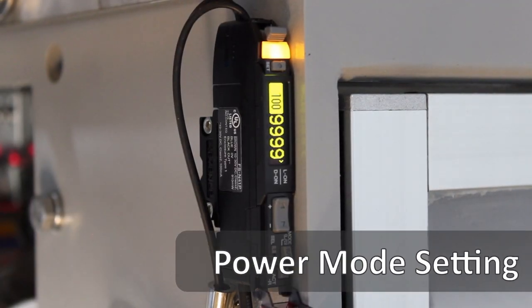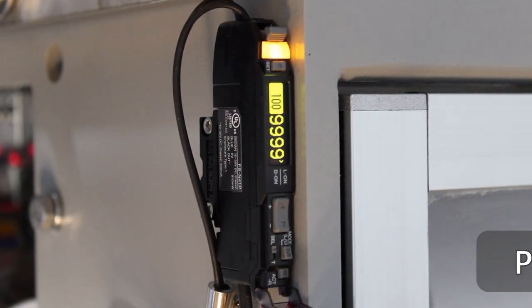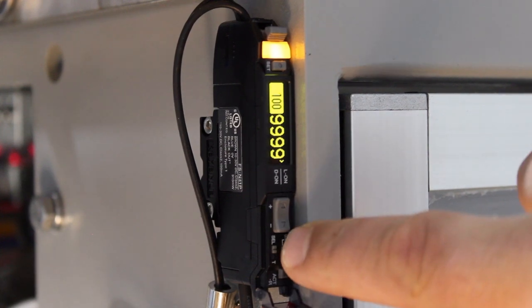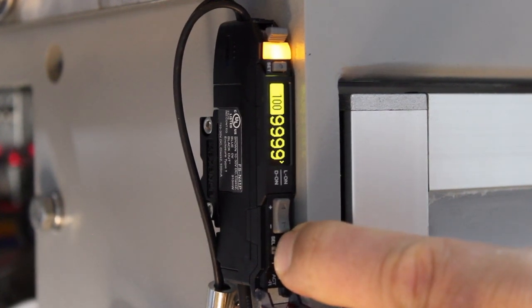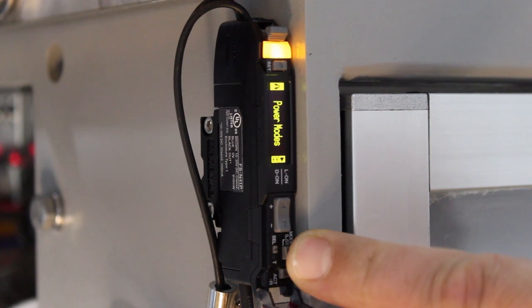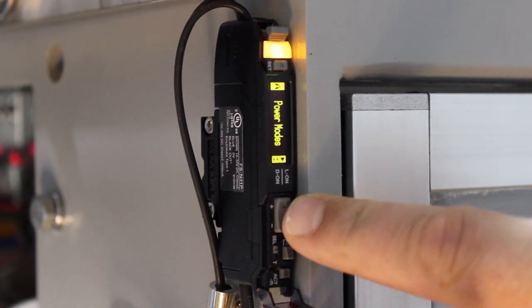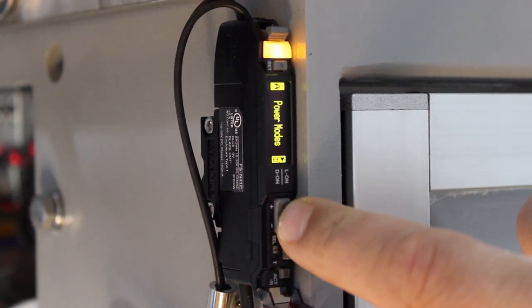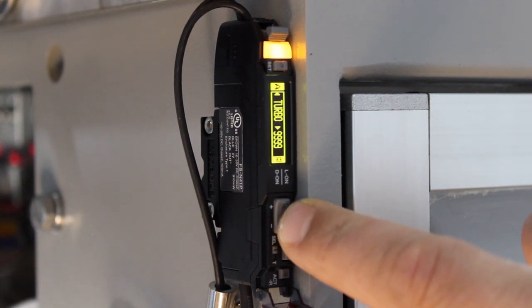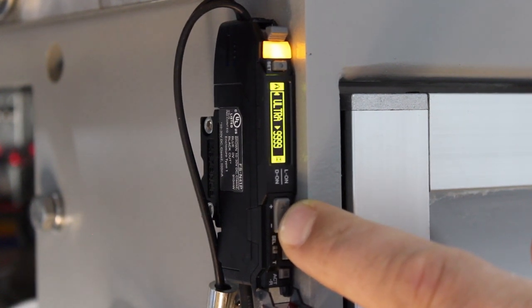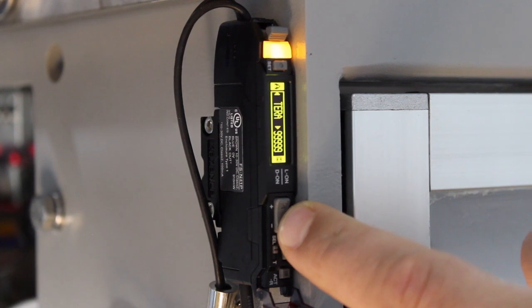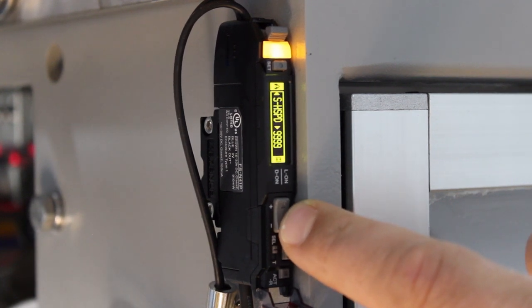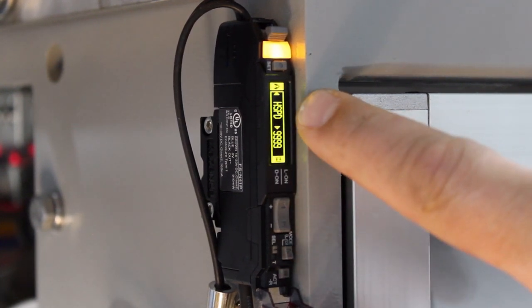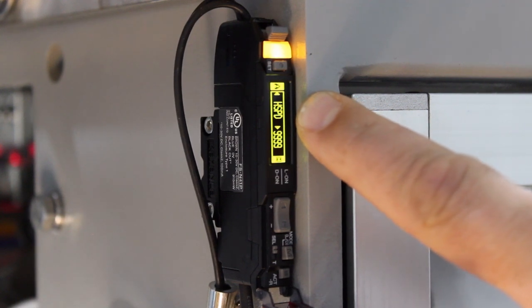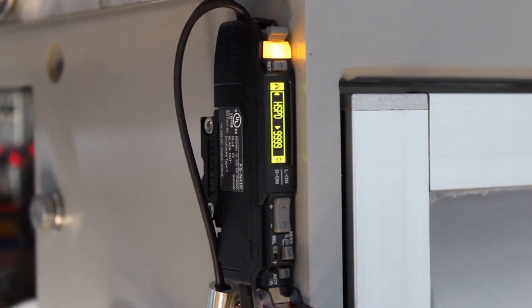In order to adjust the power mode setting, we're going to hold the M button until power mode is displayed. Press right or left until HSPD is displayed. And make sure you don't go to the SHSPD. That is the incorrect one. It should just say HSPD. And then press M to complete the setting.